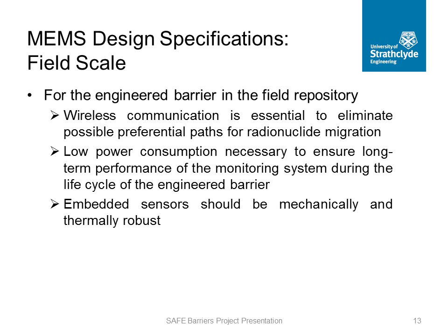Furthermore, low power consumption of the sensor is necessary to ensure the long-term performance of the monitoring system during the life cycle of the engineered barrier, as the replacement of power source is extremely difficult to achieve. In the end, the embedded sensors should be mechanically and thermally robust so that the sensors can sustain the harsh working environment inside the bentonite barrier.